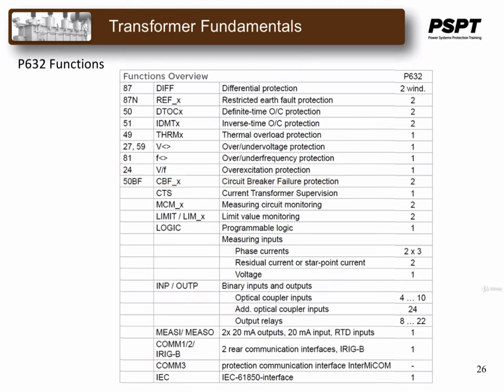As well, we have current transformer supervision, measuring circuit monitoring, limit value monitoring, programmable logic functions. They have measuring units for phase currents and residual currents and voltages, and several other options, including the communication interfaces that are standard that are out there, and it is also capable of interlocking with the IEC's 61850 interface.